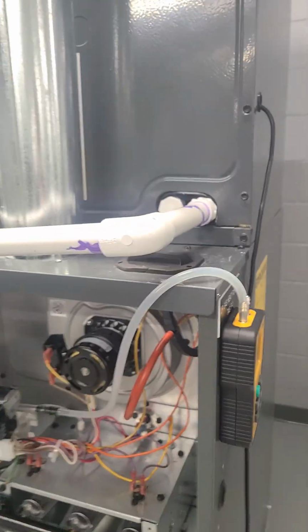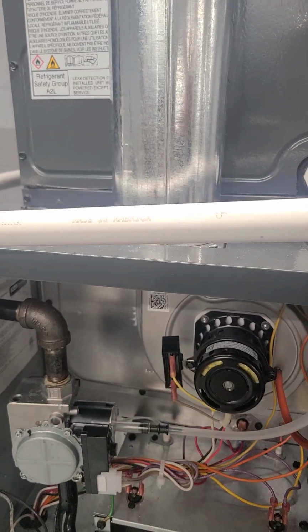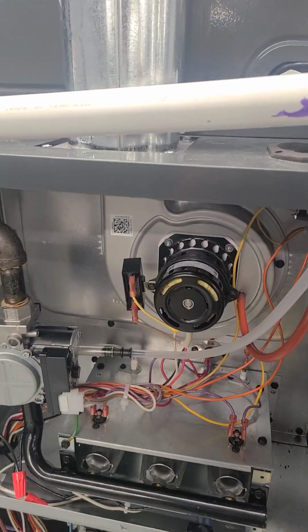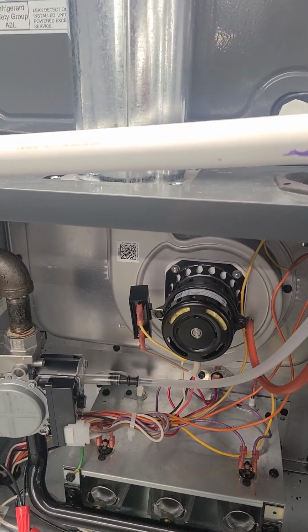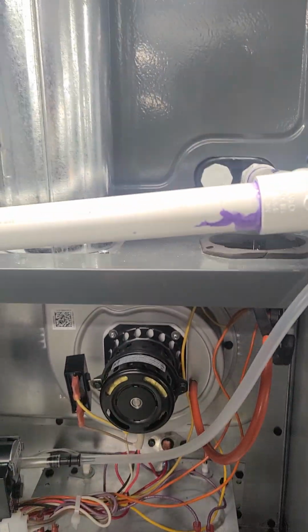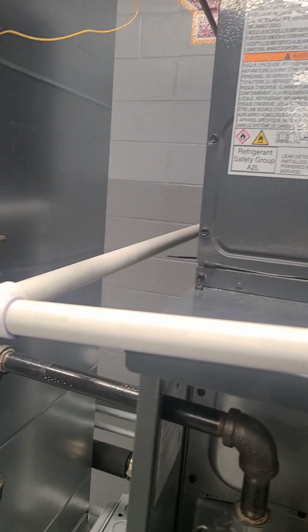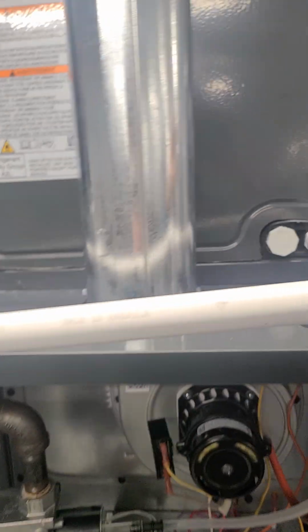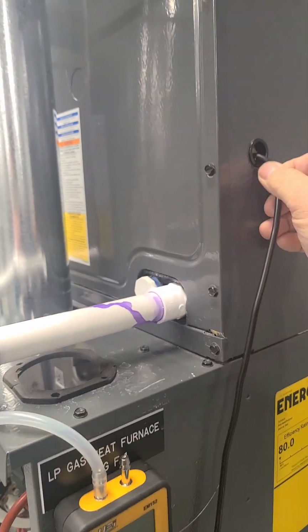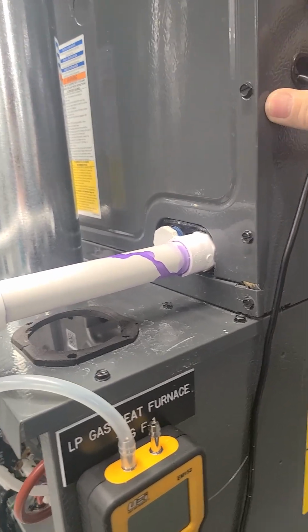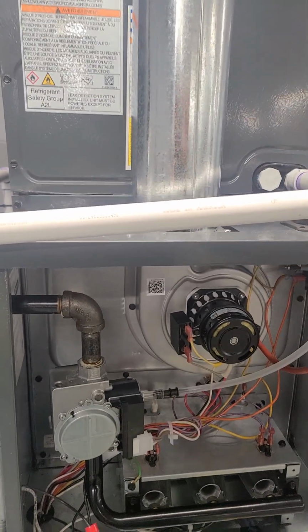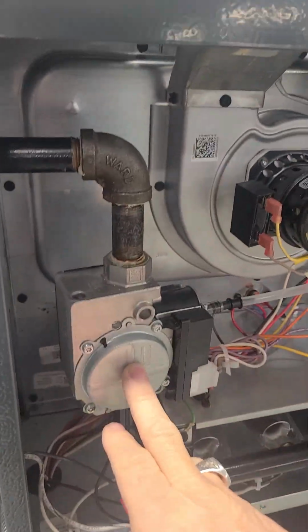Okay, and then in addition, and I know this is a furnace order of operations, however, this does involve the gas valve. So this is an A2L cooling system running R32. So there is an R32 sensor. If R32 is sensed in this unit, because it's supposed to be a sealed unit, not supposed to be sensed at all, it will shut off the signal to the gas valve because R32 is a flammable liquid.